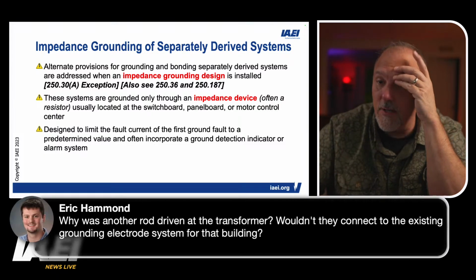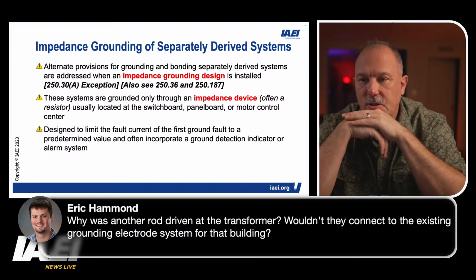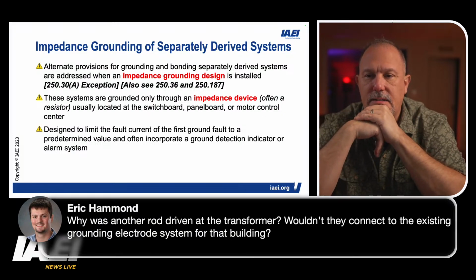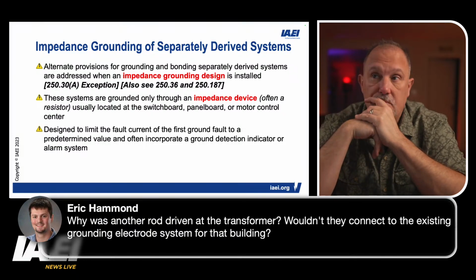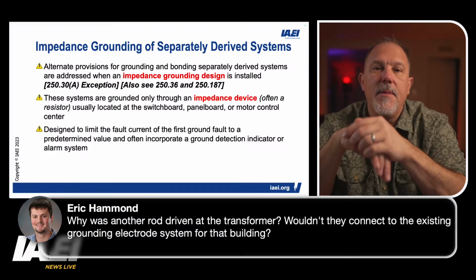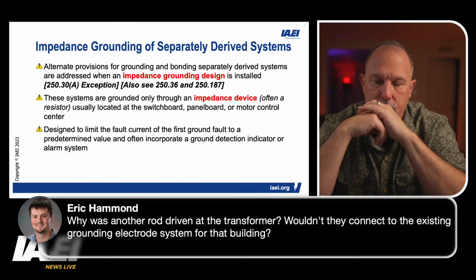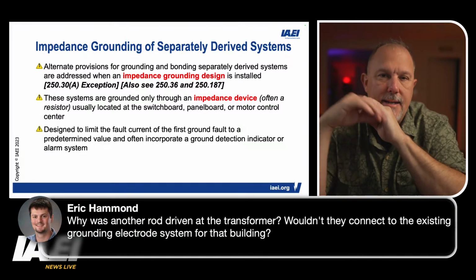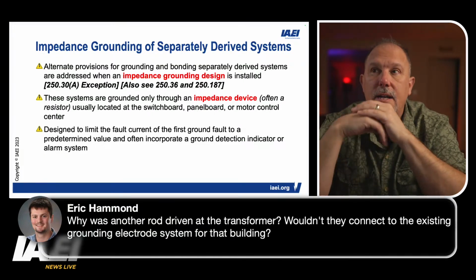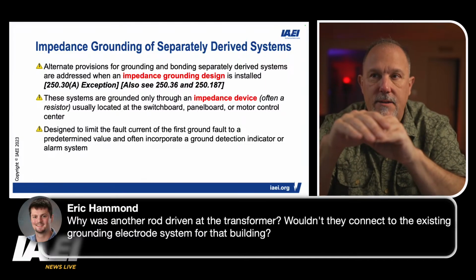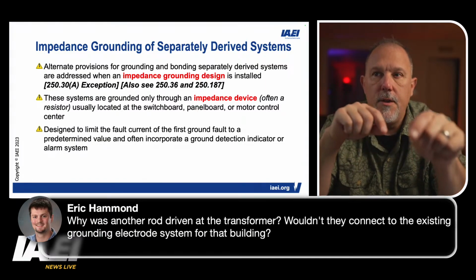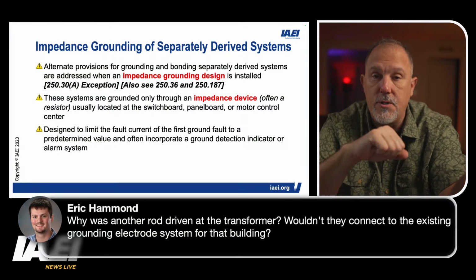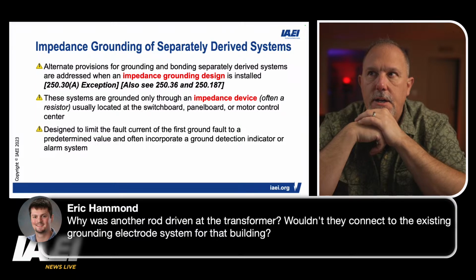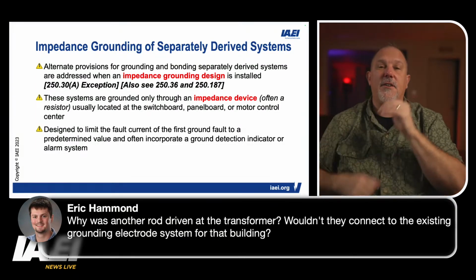So I asked this, Eric, you took the words out of my mouth. Why was another ground rod driven for the transformer? Wouldn't they connect to the existing grounding electrode system for that building? And I would agree with you, Eric. Now, I can't remember where we were at in that facility. I highly doubt I was on the second or third floor, but in any case, they could have used that rod, connected it to the building steel or whatever they were using for the grounding electrode. But I don't disagree with you.